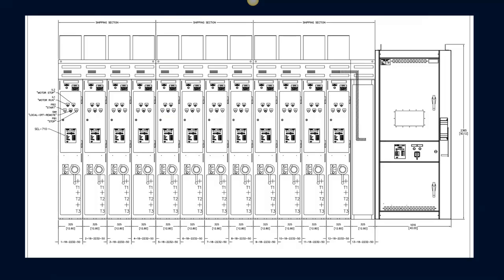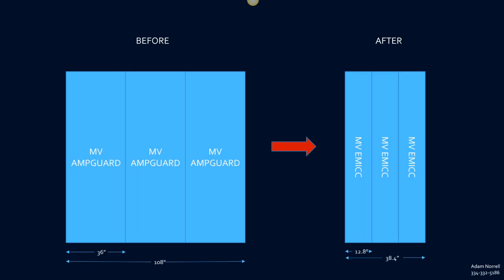Here's another drawing of that same lineup. So again, one high starters, 12.8 inch sections. And I believe they are also arc resistant. So let's just look at our footprint and what we've done here. If you remember, we had 3 motors on our one line that were across the line. And our standard, I believe a lot of people call it the amp guard gear, I think that's an Eaton or Cutler Hammer term, there's lots of other terms, but the standard across the line medium voltage starter is 36 inches wide. So we are left with a 108 inch lineup.